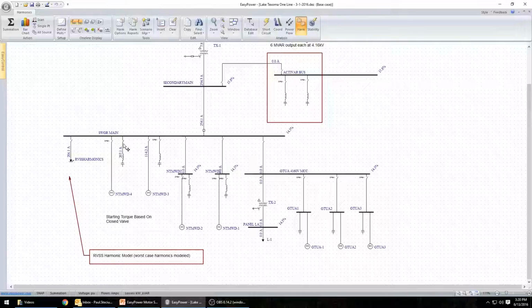So if this capacitor is on, it would represent a case where this motor was in fact starting, because you would already have one on. So we'd be in this scenario with this motor running, this capacitor on, we'd be starting this motor here. In that situation, we would see roughly 178 amps. So still a relatively significant amount of harmonic current flow into a capacitor, certainly worth looking into.